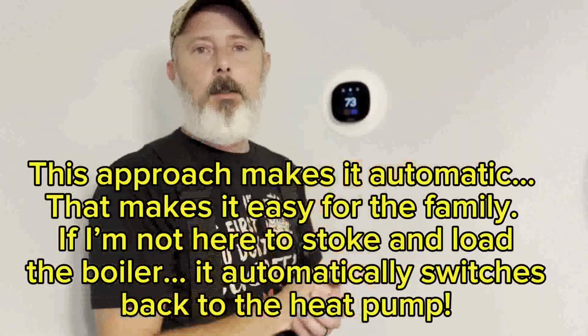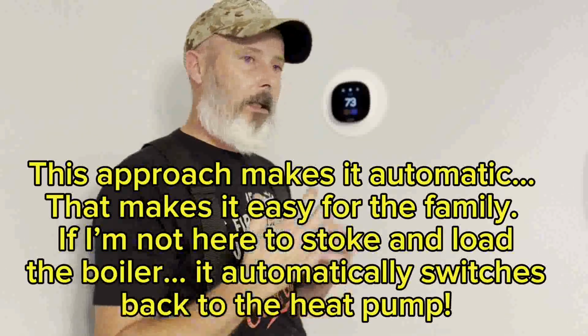So heat pumps, it basically tells two things to turn on. It tells the blower, that's the thing that moves the air, to come on, and it tells the compressor and outdoor unit to come on. So what I'm doing is if that water's hot, I'm intercepting that outdoor heat pump call. I allow the blower call to carry on, and I'm just denying that from happening. So this thermostat doesn't know where the heat's coming from. It just needs heat, turns heat on, and I'm just choosing what to turn on based off of the water temperature. If the water's good and hot, I'm going to run heat off the boiler. If the water is not hot, the call is going to carry on to the heat pump.